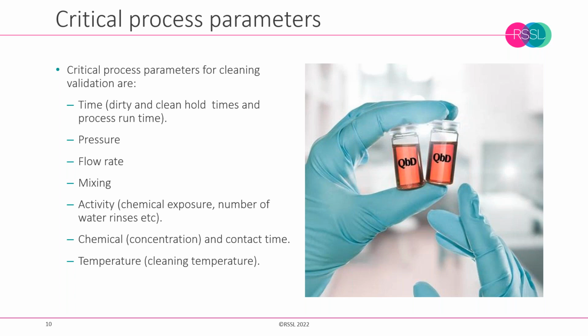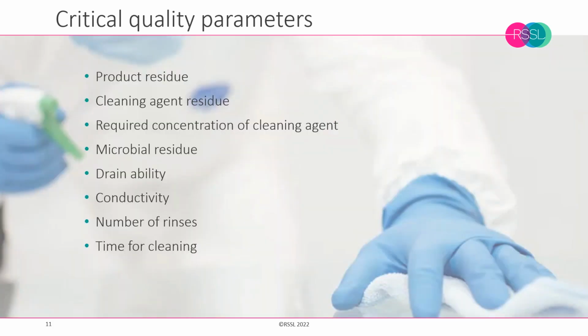And if we're looking at a manual cleaning process, then we may need additional checks as well, particularly around numbers of rinses and rinse times, and to be able to make periodic assessments of how those undertaking manual cleaning are performing and whether they're practicing everything they should, such as wiping, brushing, and so on. And we'll come back to the concerns about manual cleaning a little bit later. In terms of critical quality parameters, then we're going to have things to consider like remaining product residue, cleaning agent residues, numbers of surviving microorganisms, tests to verify that we've achieved those parameters, and also numbers of rinses and the overall cleaning run time.